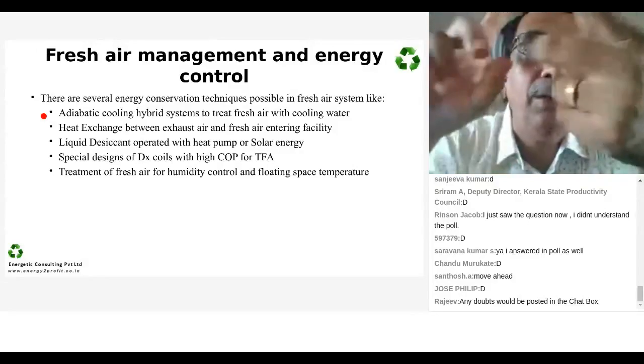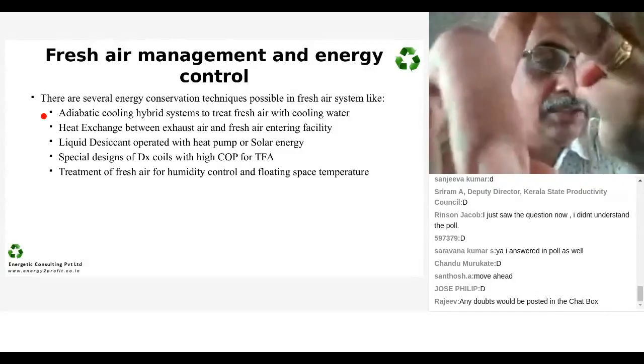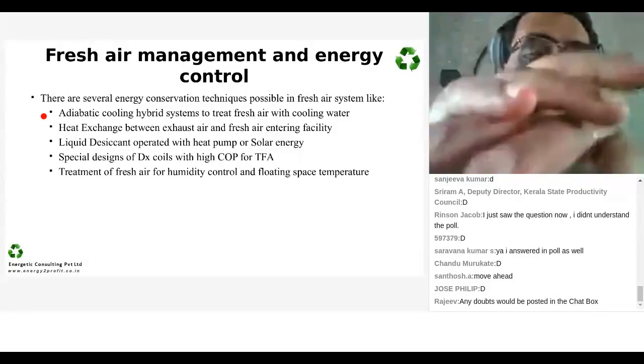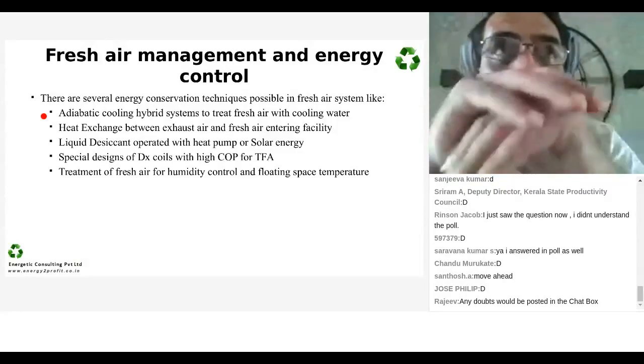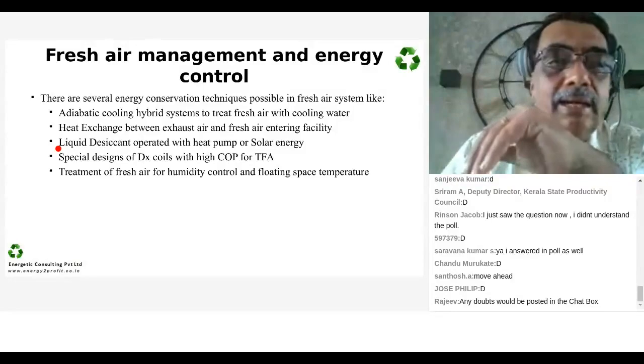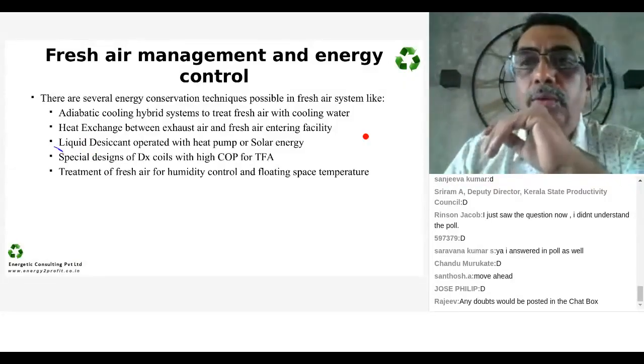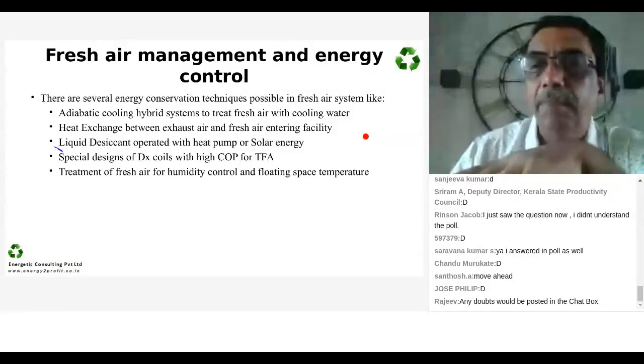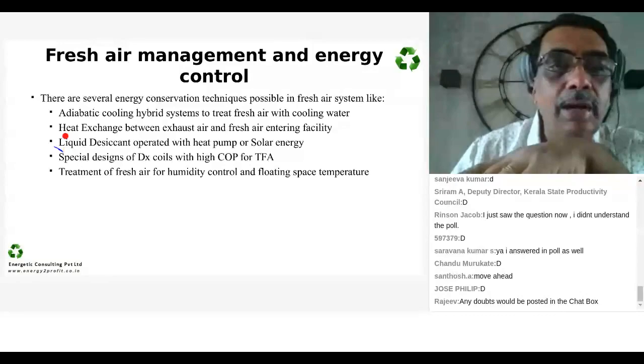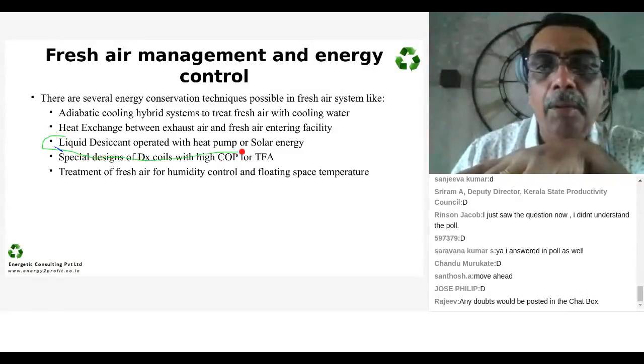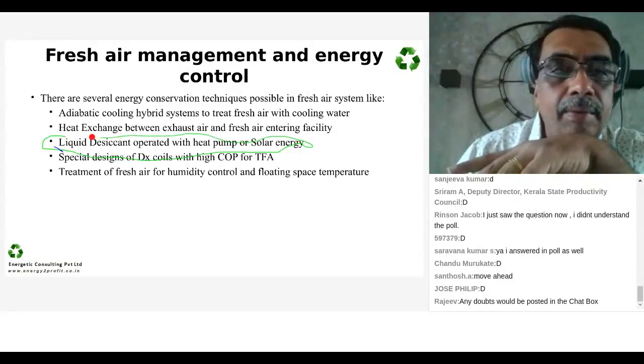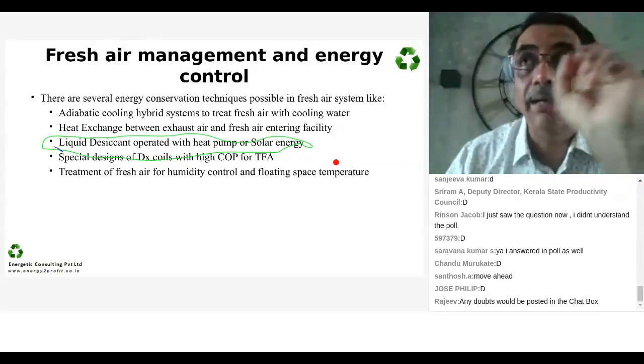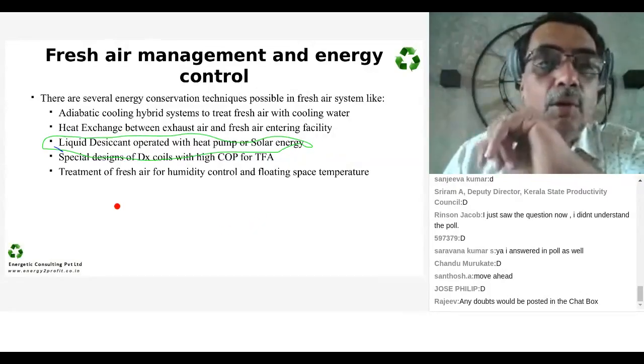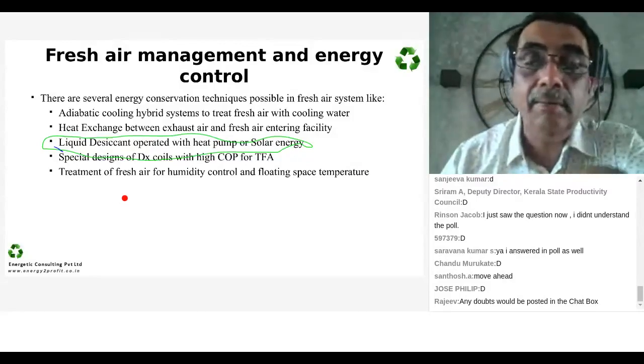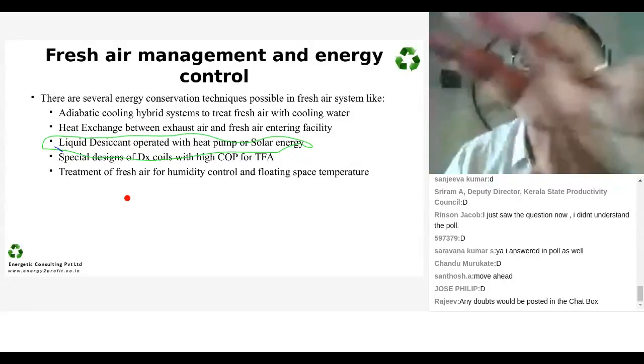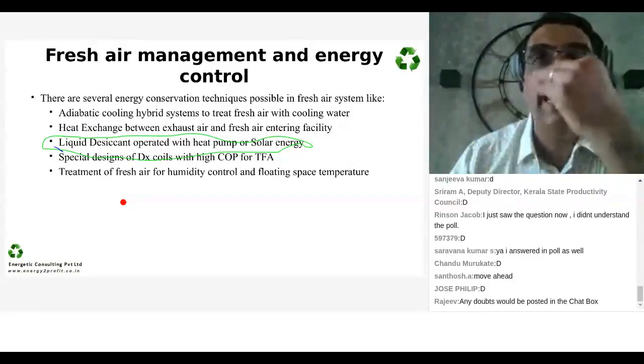If you have a hospital, you have a hotel, you have an industry, you have any kind of load in Kerala, you must, like Goa, like Mumbai, like Chennai, these are the places where technologies like liquid desiccant have to be taken into account, because these are the greener parts of technology where you are taking care of the culprit, that is water in air, by using chemical desiccant and not the refrigeration. I'm going to have a case study, so I will talk about it in that. Then there are special design DX coils where refrigerant is directly used to do air treatment and cooling. These are also designed to control humidity.